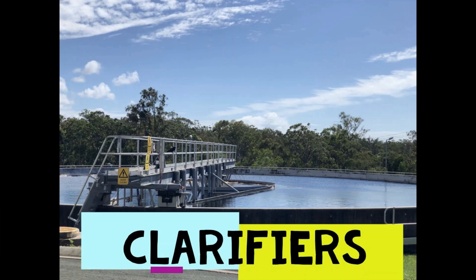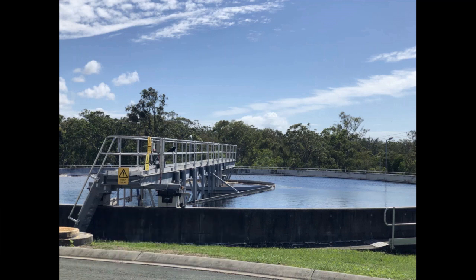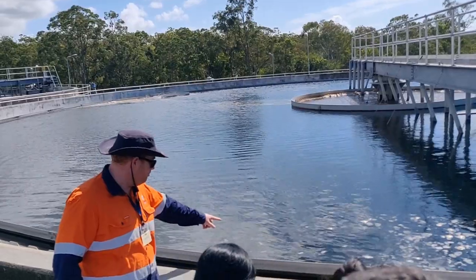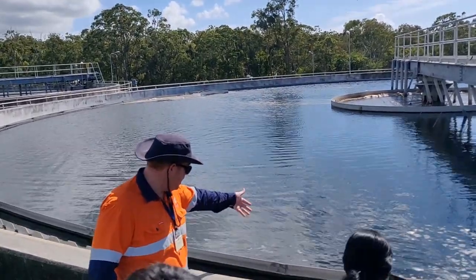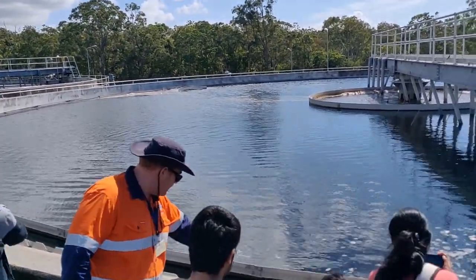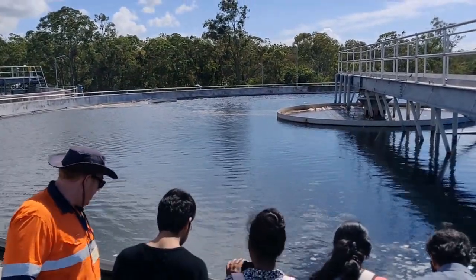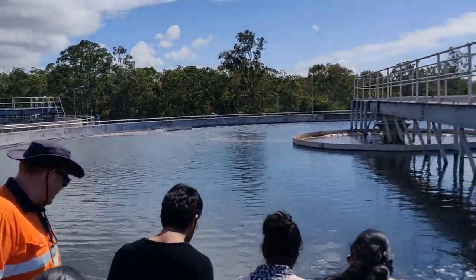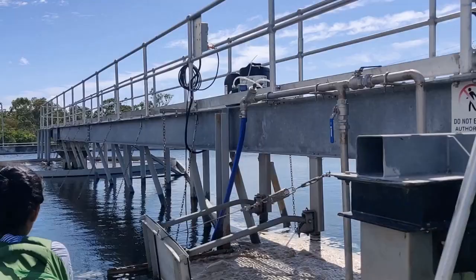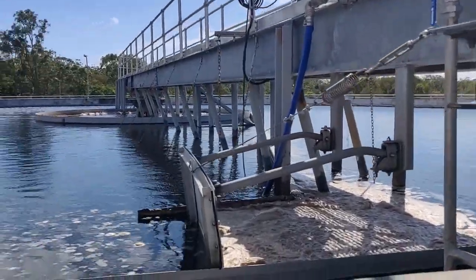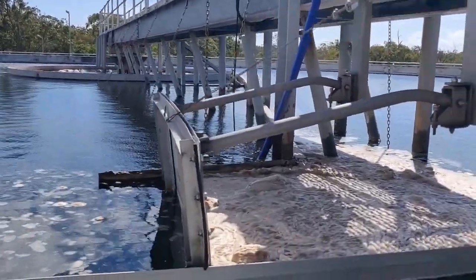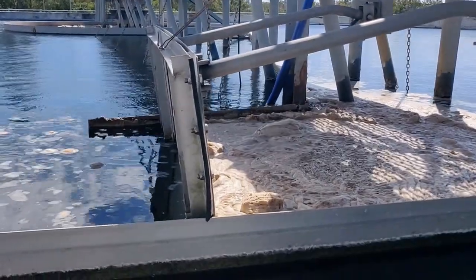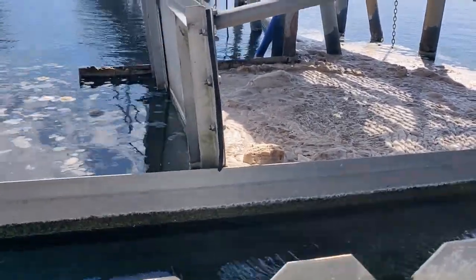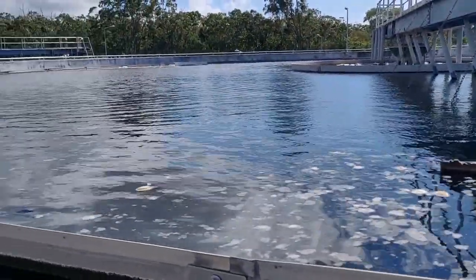Clarifiers. The flocculated larger particles settle down inside the clarifiers by gravity. The speed of the water moving around inside this clarifier is around 1 meter per hour. The diameter of the clarifying tank used in the Rajan plant is about 32.5 meters and the volume is 2.6 megaliters. It generates both activated sludge and clean water. The activated sludge is taken back into the bioreactor.